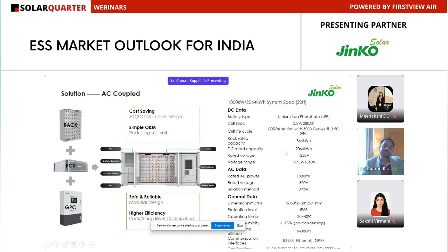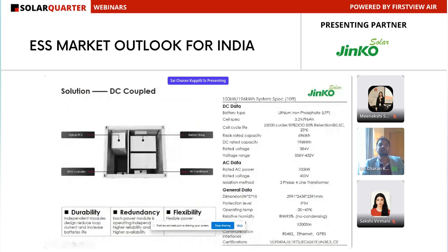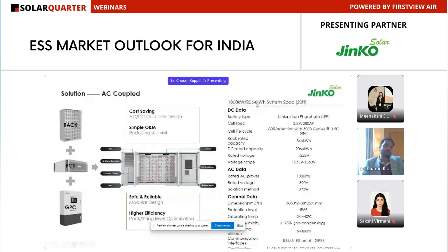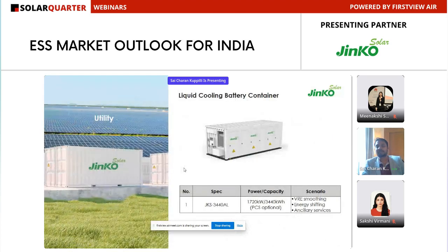There's a typical specification of a 2 megawatt hour solution which comes with 1 megawatt AC output, as an AC coupled 20 feet container solution. The same thing for a DC coupled system is limited to only 100 kilowatt per container, with a maximum of 200 kilowatt hours output. So application-wise, if your requirement is limited to small capacities, DC coupled systems make comprehensive sense. But if you have a specific requirement at megawatt hour scale, AC coupled systems make more comprehensive sense, and they are highly reliable and a plug and play system.